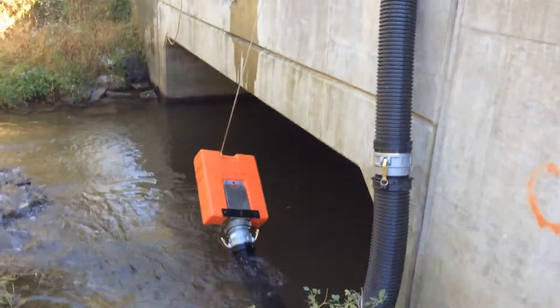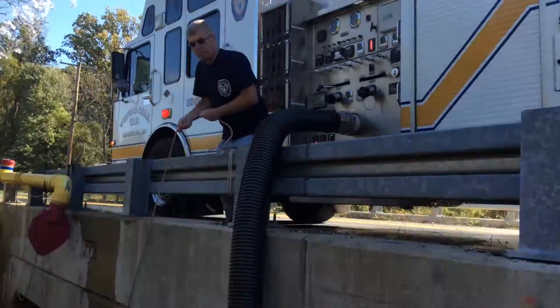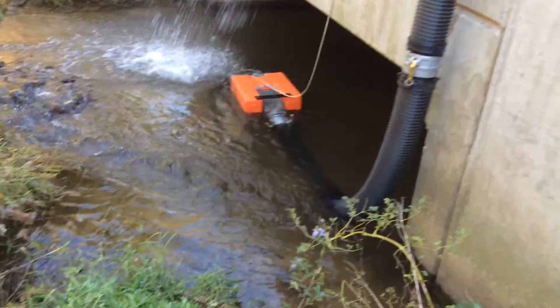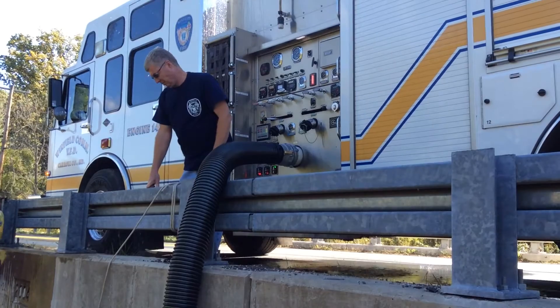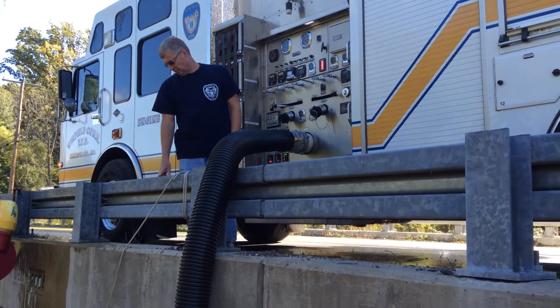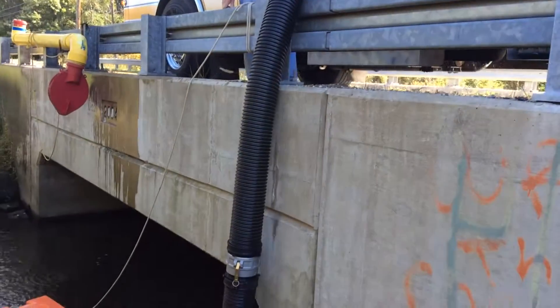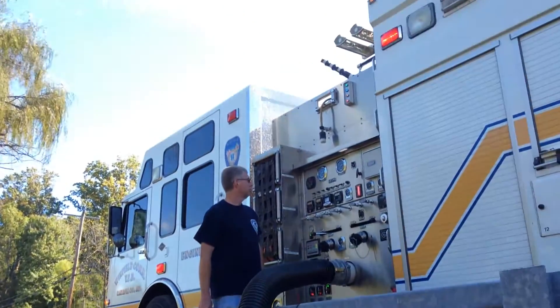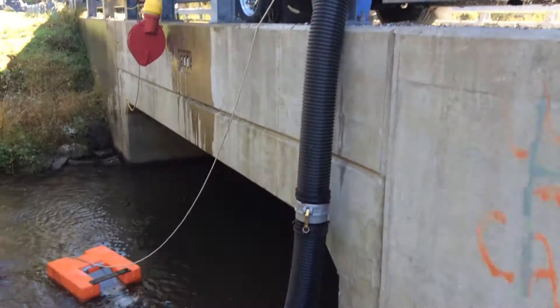The prime is broken. We're going to lose water here in a moment. All right, we lost water. You can put the strainer back in. You can hear the primer automatically activating. Again, the driver operator is not touching that panel at all. And we should see water coming back up — and we're back to flowing water again. Pretty impressive operation.